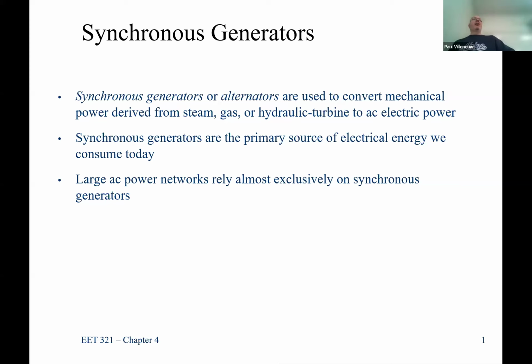So a gas turbine works very differently than a steam turbine. In a steam turbine, you have the expansion of the steam, which reduces its energy, and then in a condenser you take it back to water and send it back to the boiler. A gas turbine doesn't have a separate boiler like that - there are nozzles that blow in natural gas, which is ignited, and that's the source of energy. So the steam turbine and boiler, or the firing mechanism, are all sort of one package.